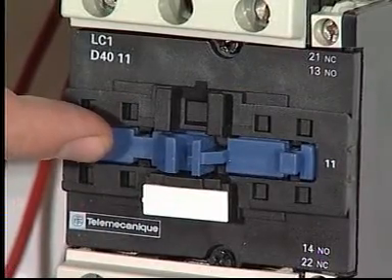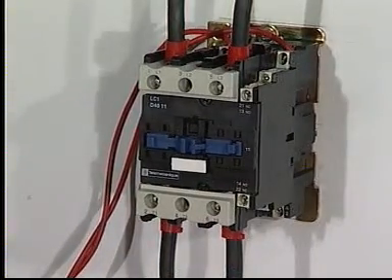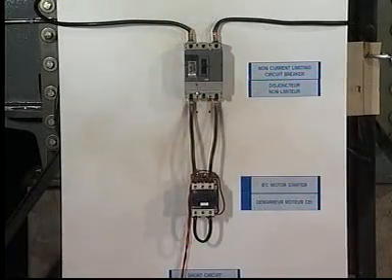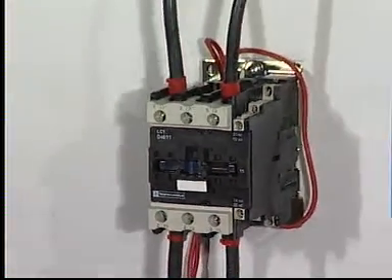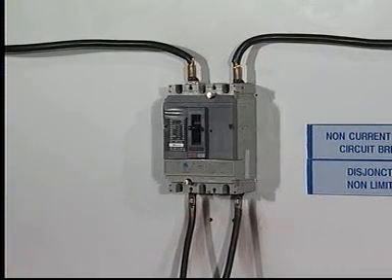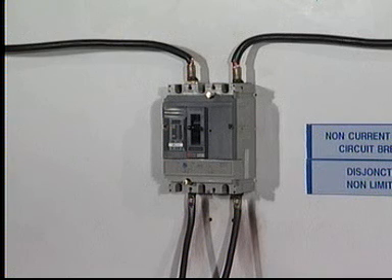As you can see, the contacts are fully functional before the test. The ionized product can be seen outgassing from the breaker's arc chutes as it opens the circuit. Inspection indicates that the starter contacts appear to be welded. The protection level is Type 1 protection, meaning simply that the component damage is restricted to within the component and that the component is not reusable.